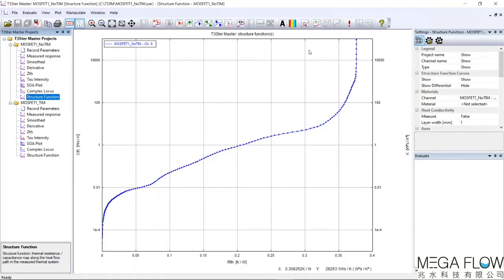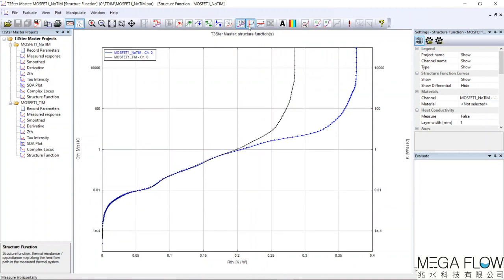By repeating the same measurement with two different thermal interfaces or flow rates, the two thermal transient curves will overlap until the heat reaches the changed interface. The desired thermal resistance can be read at the divergence point of these two curves. The extracted thermal RC network can be used to generate a compact thermal model for simulation purposes or serve as a reference for the fine-tuning of detailed 3D thermal model parameters.